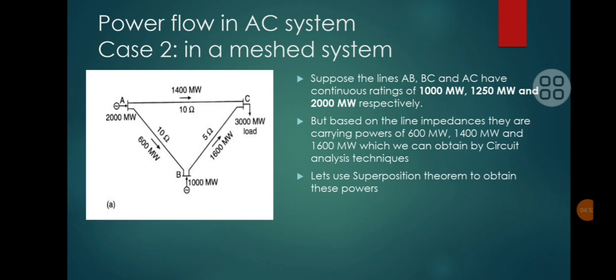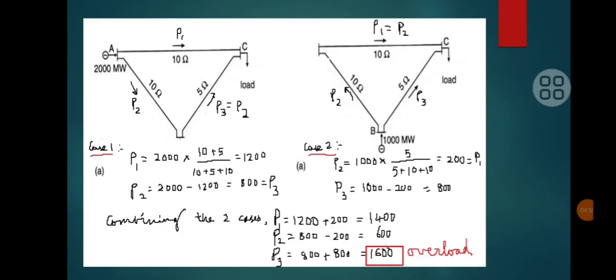By using the superposition theorem, we can get these values. Here I have shown the superposition principle implementation. Case 1 is where the generation at A is retained, but the source at B is removed, and powers are calculated. We get P1, that means line AC power, as 1200, and P2 and P3 as 800 megawatts. In case 2, we remove the generation at A and put the generation at B back. In this case, we get the powers P1, P2 according to the current division rule as 200 megawatts and P3 will be 800 megawatts. Finally, based upon the superposition principle, we combine these two cases.